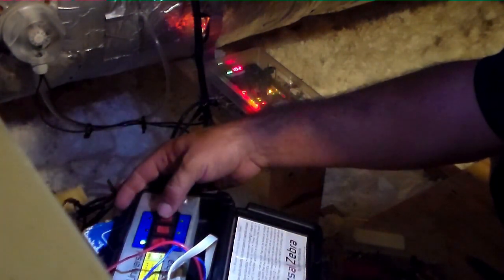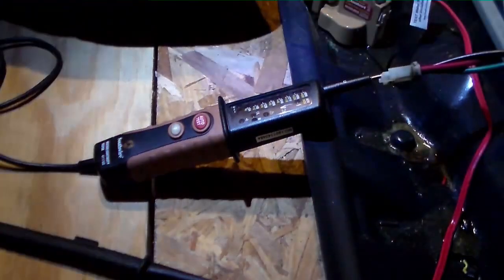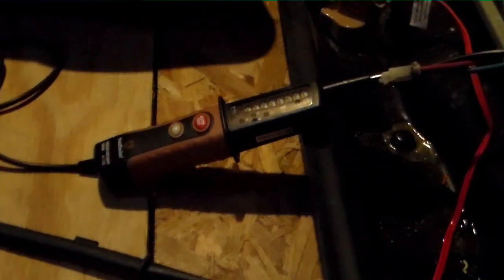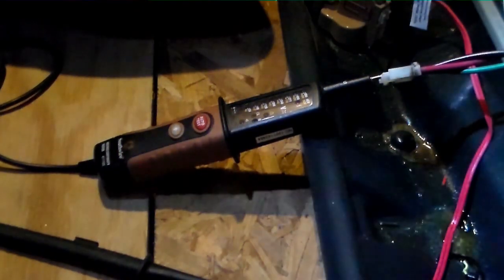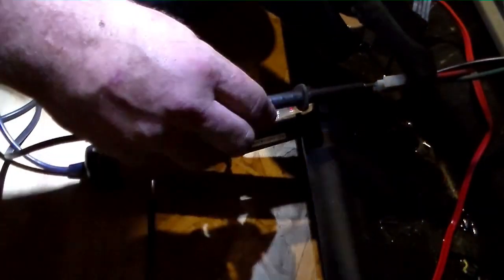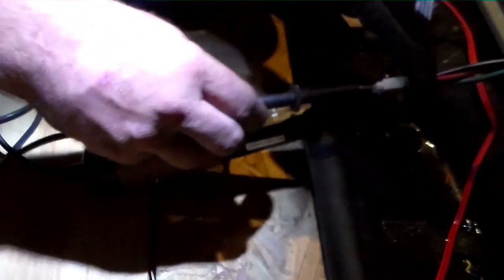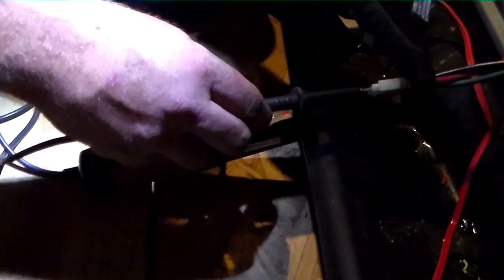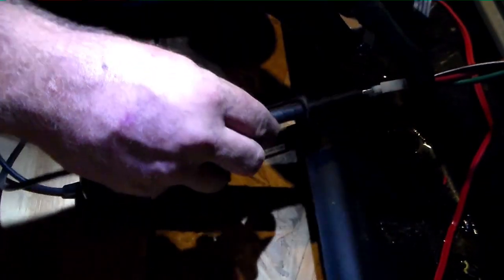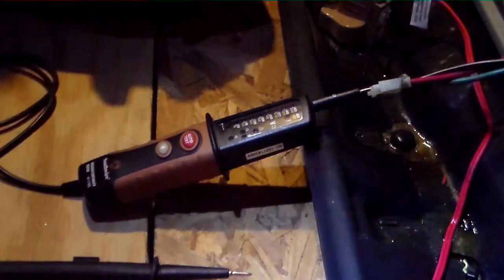So far we've got no action on the variable speed blower. Double check high voltage to that blower. Alright guys, I have my voltmeter here. We'll turn this back on. See what we got. So we have to have power to the fan. We have 120 volts to the fan motor there. We have 120 volts there. So we have power to the fan motor, and it is just not looking very good.